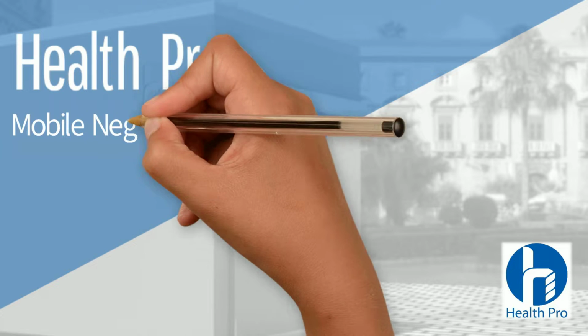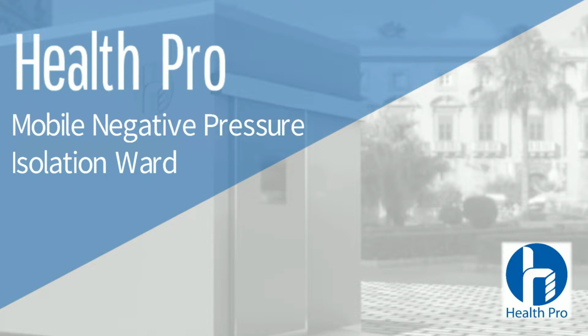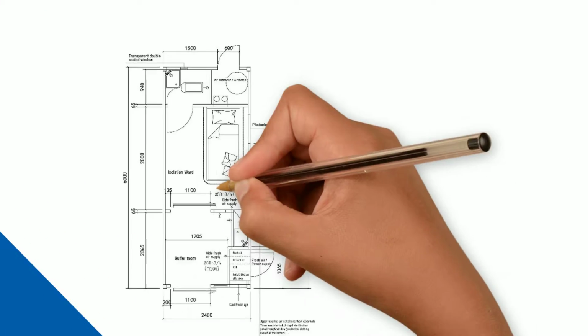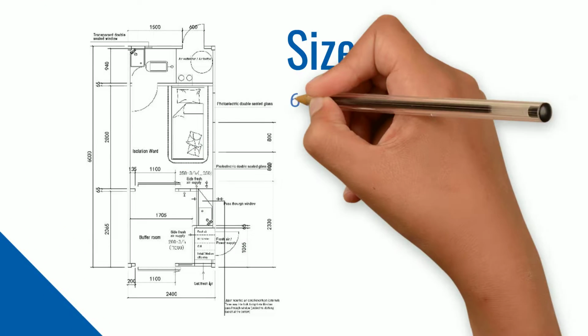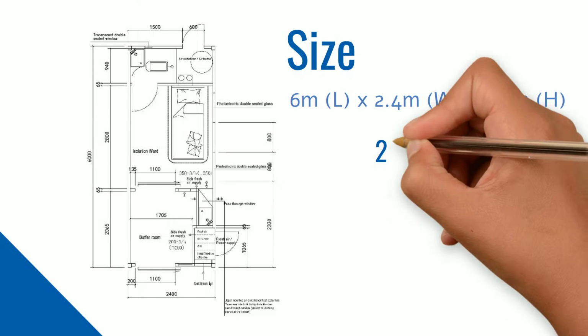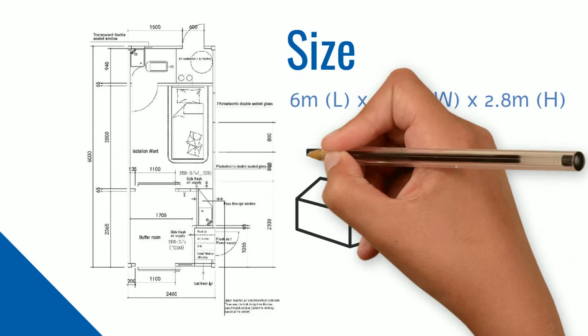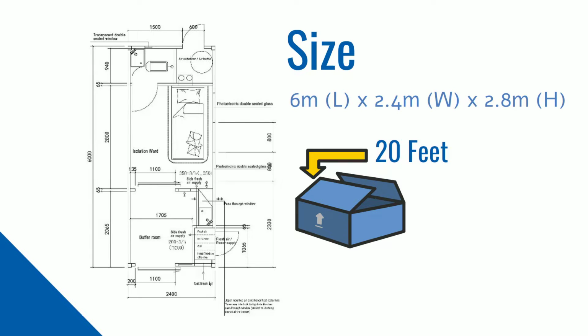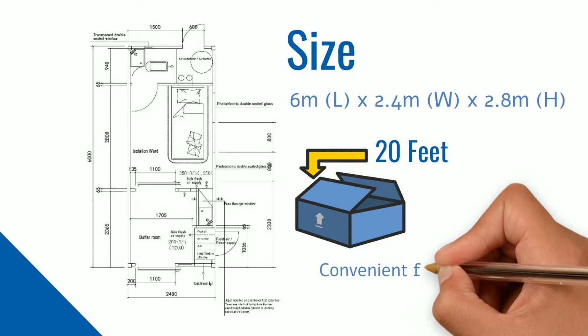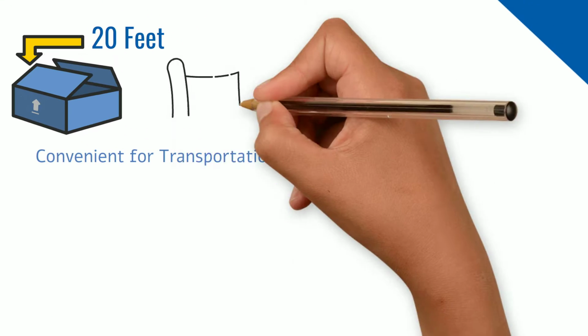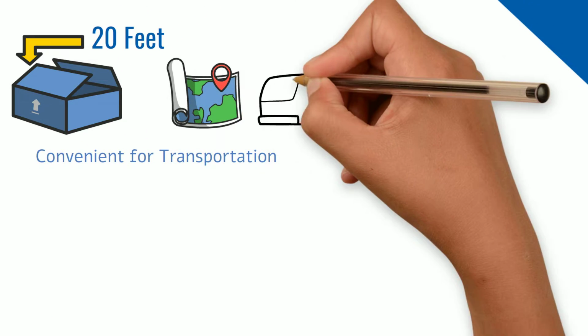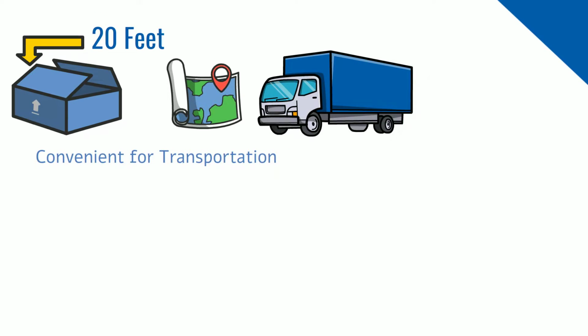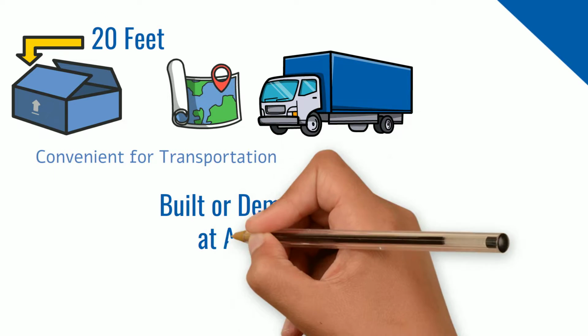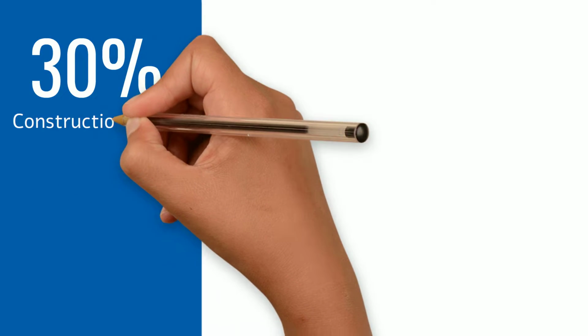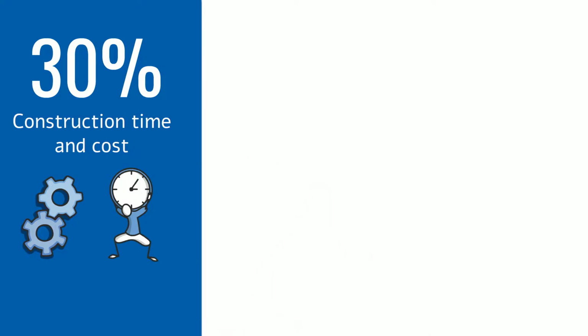Recently, the Health Pro Mobile Negative Pressure Isolation Ward was designed under the epidemic situation. The negative pressure isolation ward is 6 meters times 2.4 meters times 2.8 meters in size, which is the same as a 20 feet container box. Assembling the ward into the form of a container box is convenient for transportation, and it can be transported easily to the virus outbreak cities by a container truck. Meanwhile, this assembled construction can be built or demolished at any time. In other words, this arrangement can save about 30% of construction time and cost.